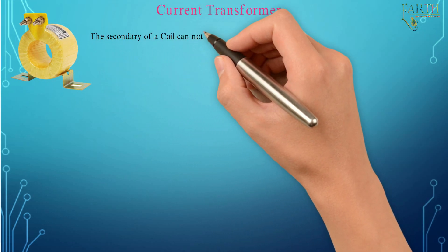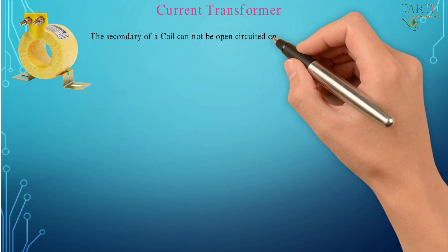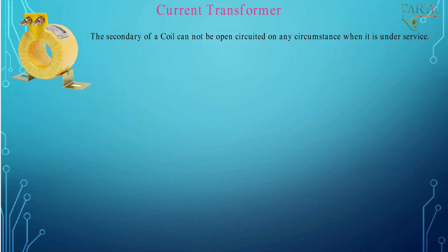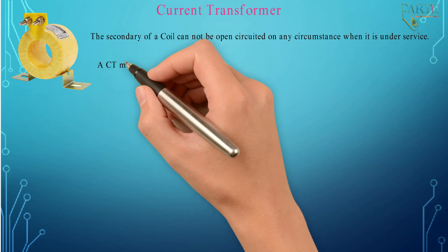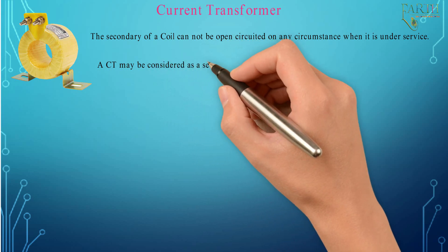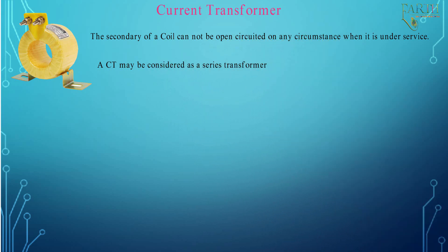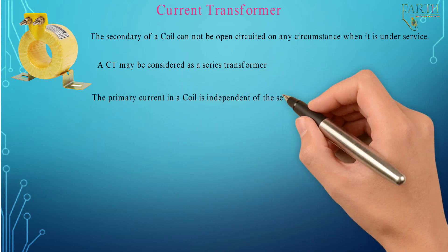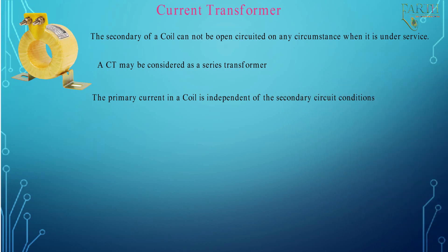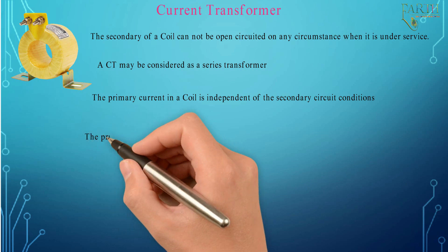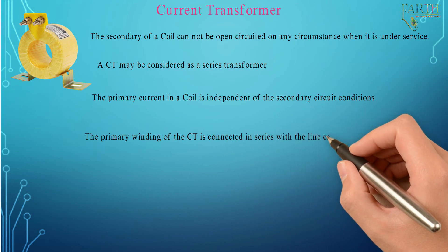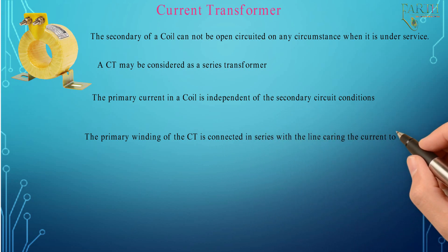The secondary of a CT coil cannot be open-circuited under any circumstance when it is in service. A CT may be considered as a series transformer. The primary current in a CT is independent of the secondary circuit conditions. The primary winding of the CT is connected in series with the line carrying the current to be measured.